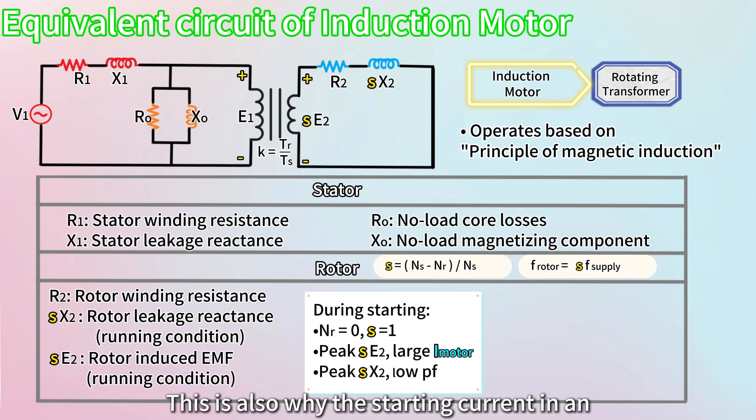This is also why the starting current in an induction motor is much higher than during normal operation due to the high induced EMF at startup. Moreover, the motor starting power factor is very low because of the high rotor reactance in the initial stages.